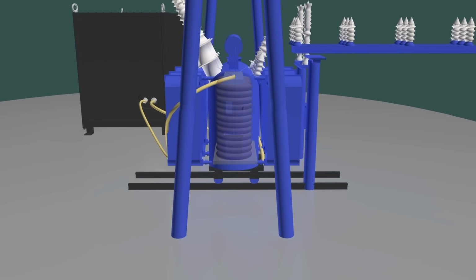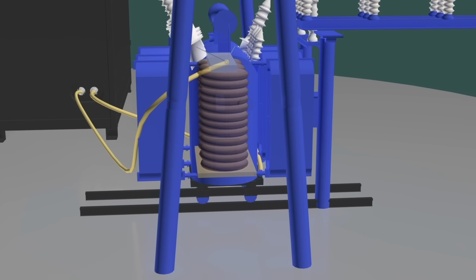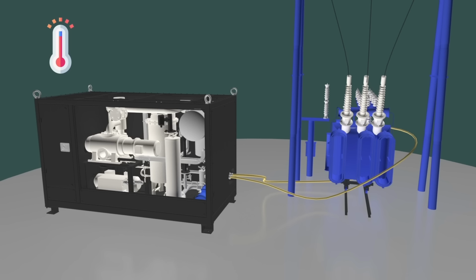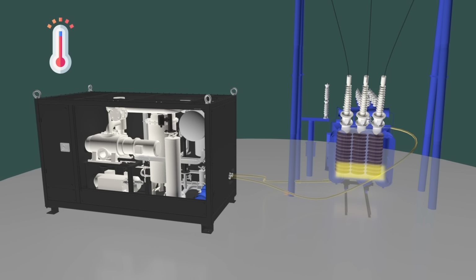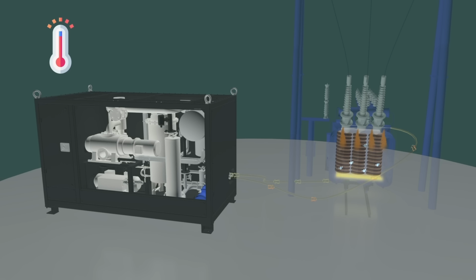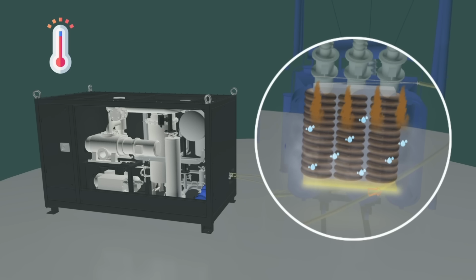transformer tank. After that, the oil from the transformer tank bottom is fed through a filter into the heater, where it is heated and sprayed onto the transformer windings under the pressure of 2.5 bar, thereby ensuring that the windings are flushed and evenly warmed up. As a result, moisture begins to exude even from the deepest layers of insulation.